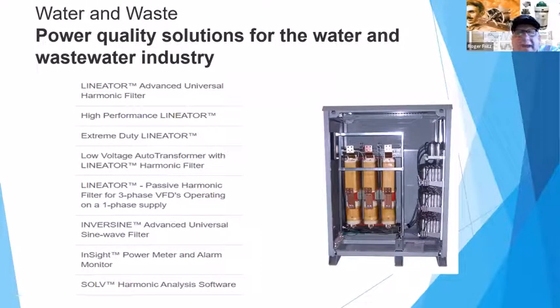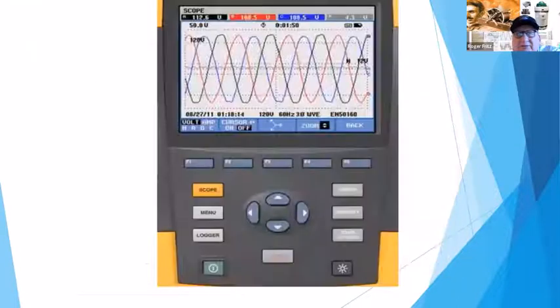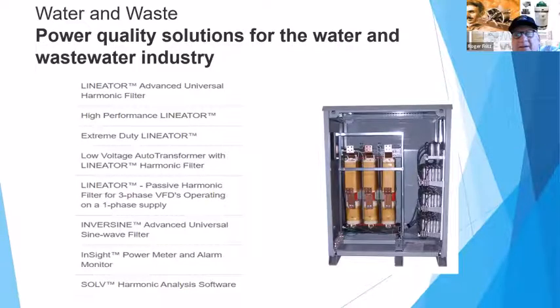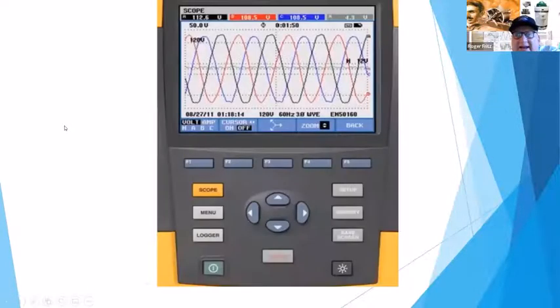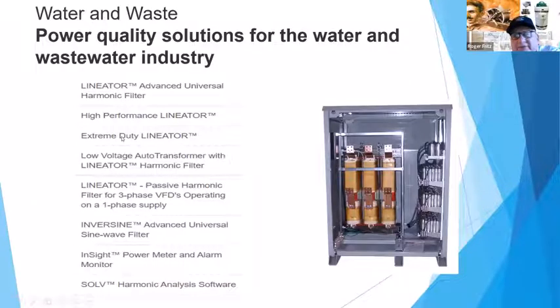So what's happened from that point is, after we get to the VFD and you create that PWM, it's important to also understand that when you get a distance away from a variable frequency drive, you also take into consideration what that output waveform actually looks like, and where the peaks are going to be. So there is also a need for what they call harmonic filters.